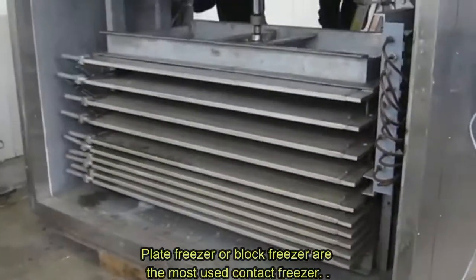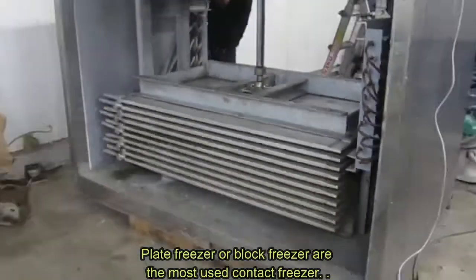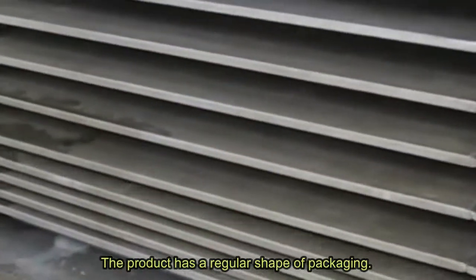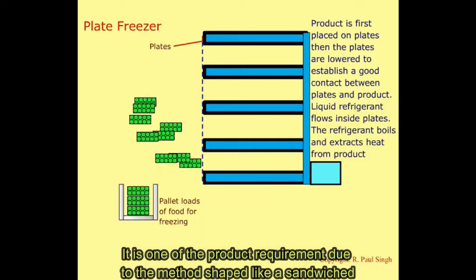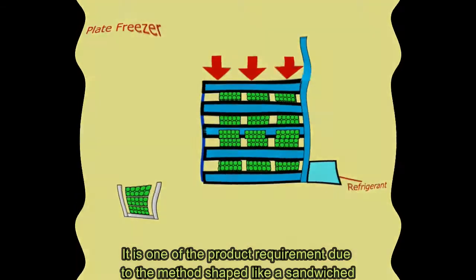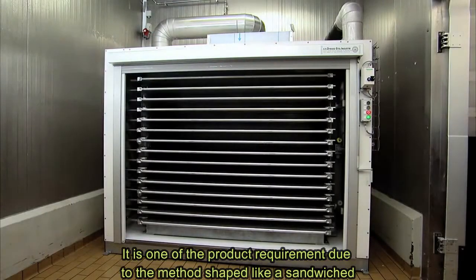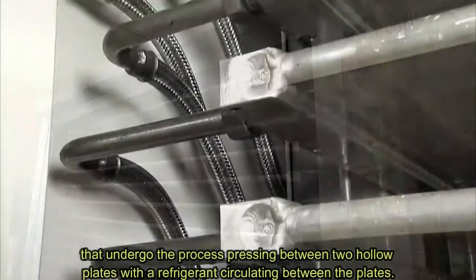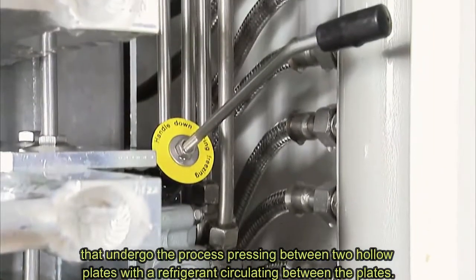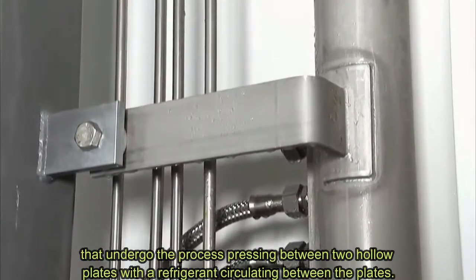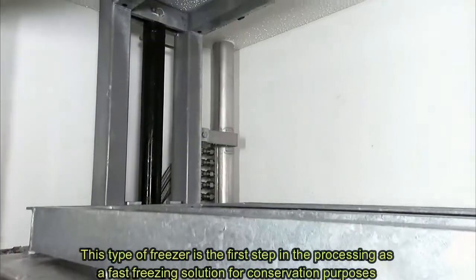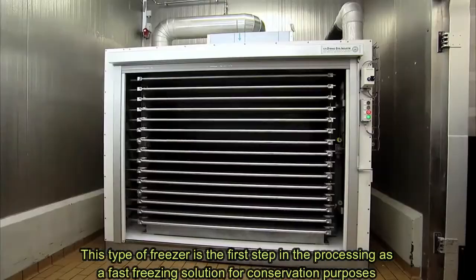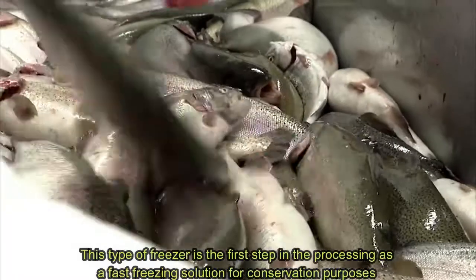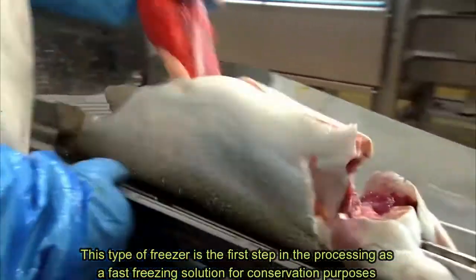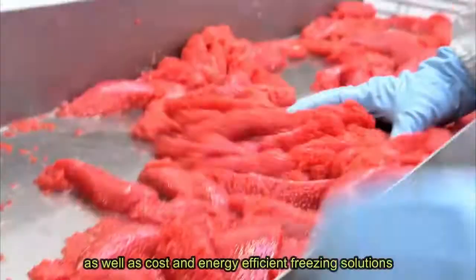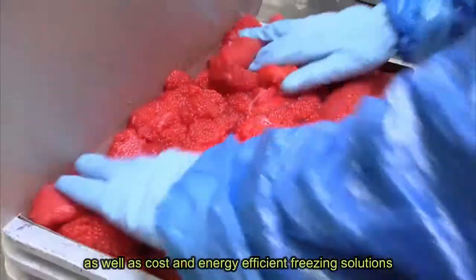Plate freezers or block freezers are the most used contact freezers. The product has a regular shape of packaging. It is one of the product requirements due to the method, shaped like a sandwich, that undergoes the process between 2 hollow plates with a refrigerant circulating between the plates. This type of freezer is the first step in the processing as a fast freezing solution for conservation purposes, as well as a cost and energy efficient freezing solution.